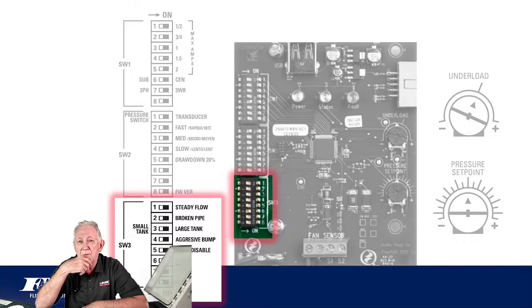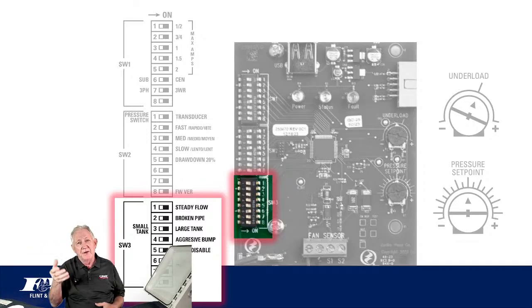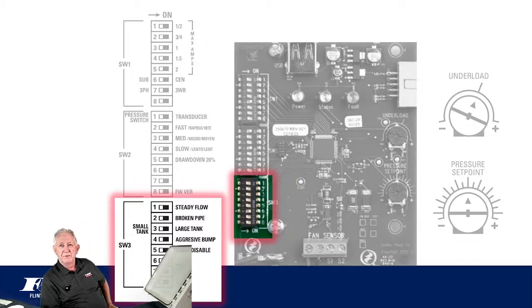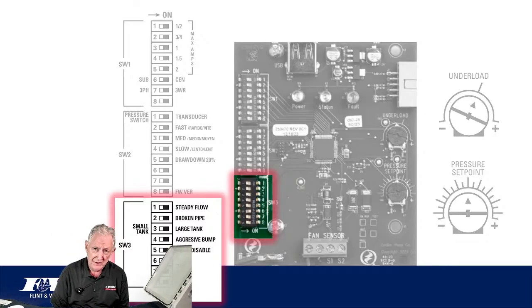That bottom bank, there are times where this drive will be installed and nothing on that bottom bank will ever need to change at all. There are occasions where we would, but the majority of the time not. In that second bank, you're choosing a transducer or a switch. And by the way, if you don't tell the drive what it's got, it'll figure it out. It'll determine whether it's got a transducer or a switch involved.